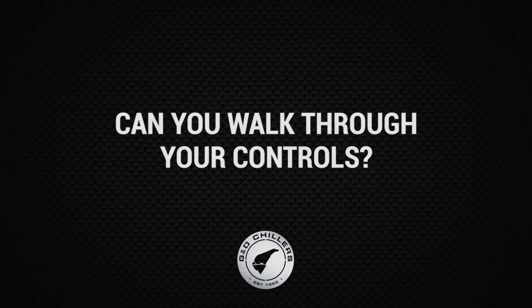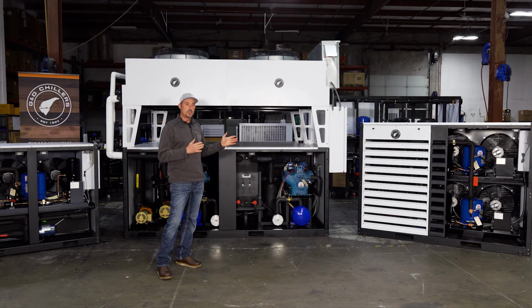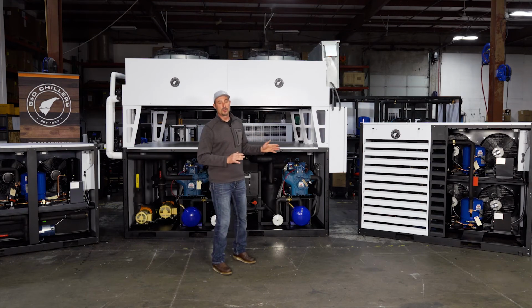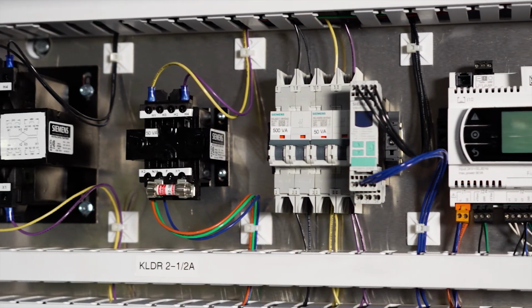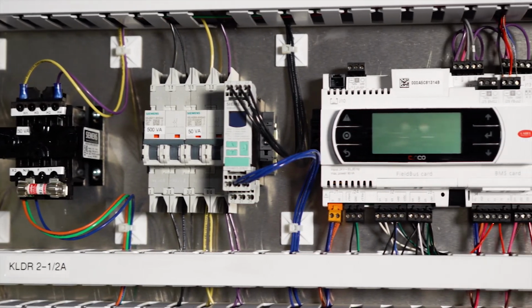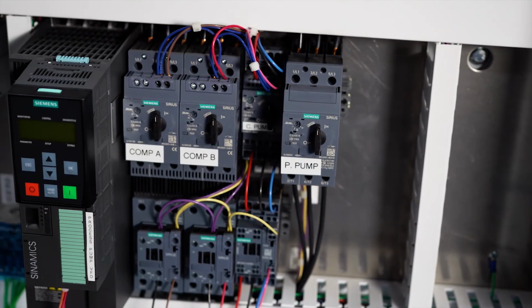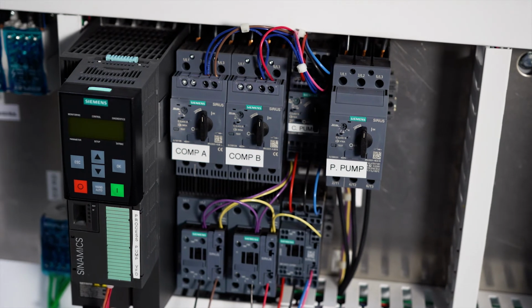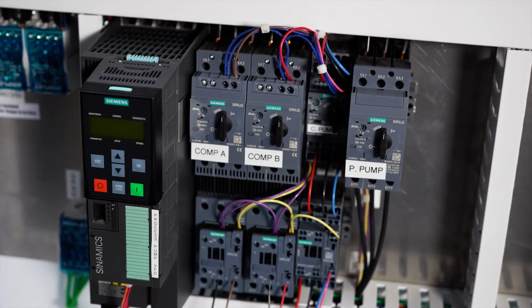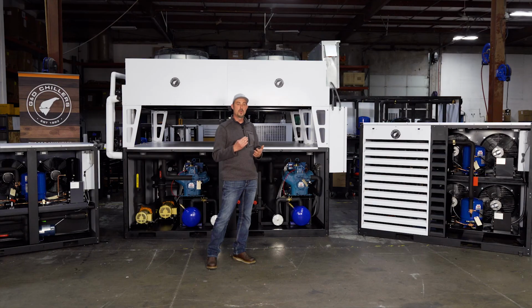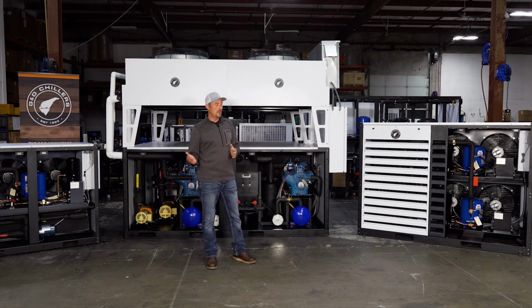With our control panels, where you're actually going to hook the power to our chiller, we try to make it as simple as possible. And again, getting back to proprietary parts, there's nothing in our control panels that is proprietary. One thing that we do differently than a lot of other chiller manufacturers is we use circuit breakers instead of fuses. There's nothing wrong with fuses. They protect motors just like a circuit breaker, but with a circuit breaker you have a little bit more level of sensitivity and protection against bad power brownouts, 3-phase dropouts.